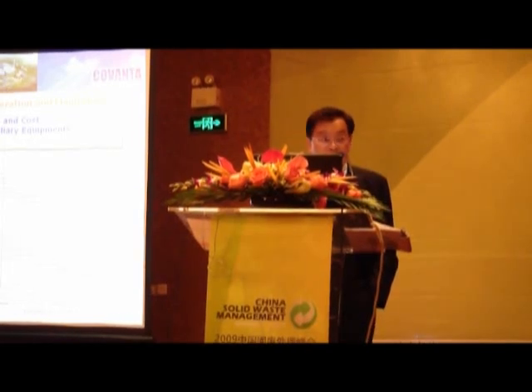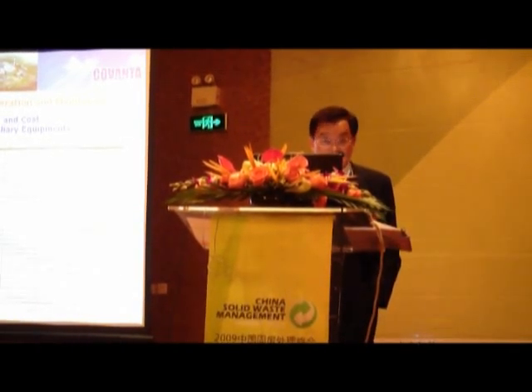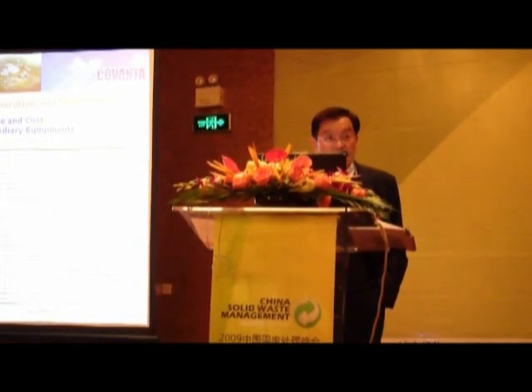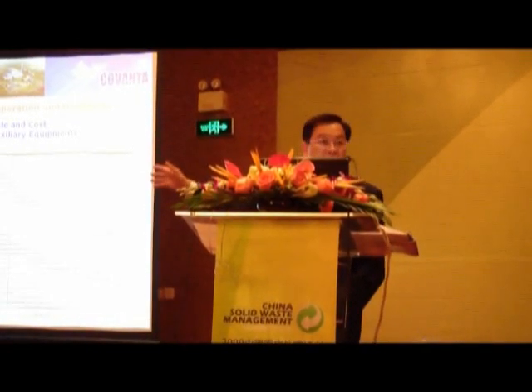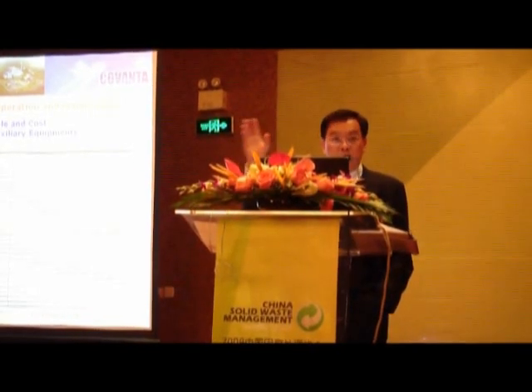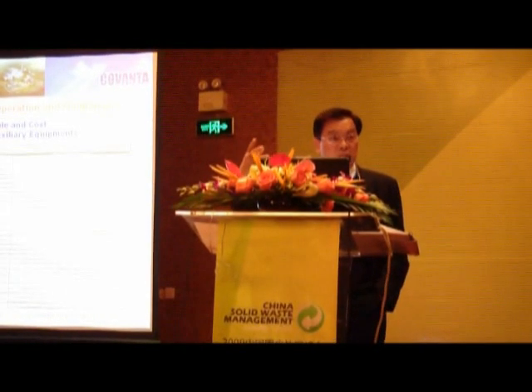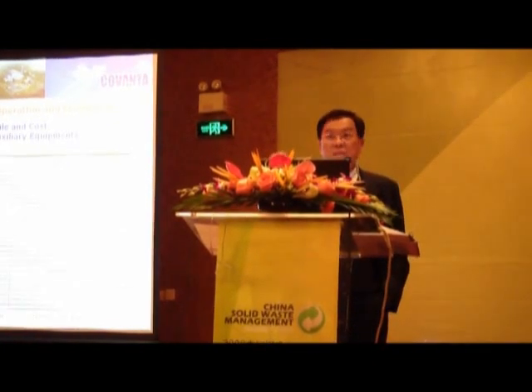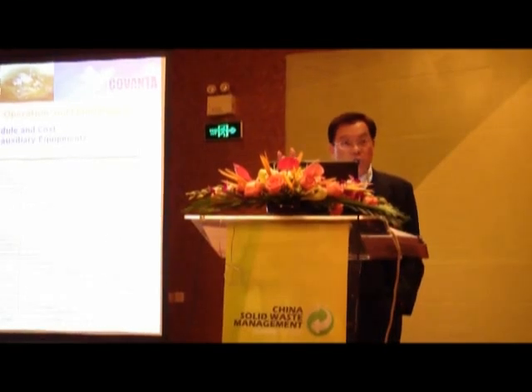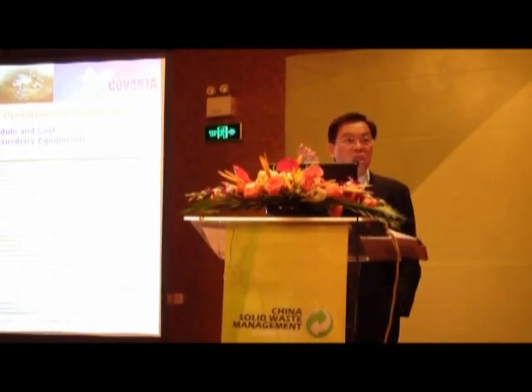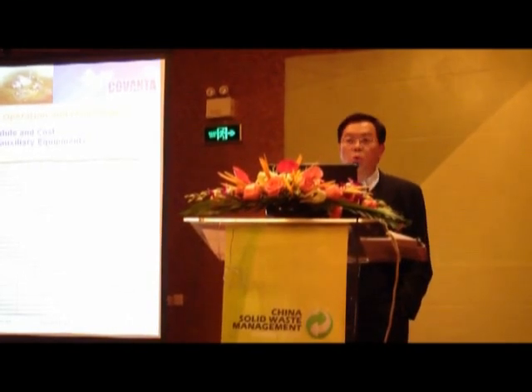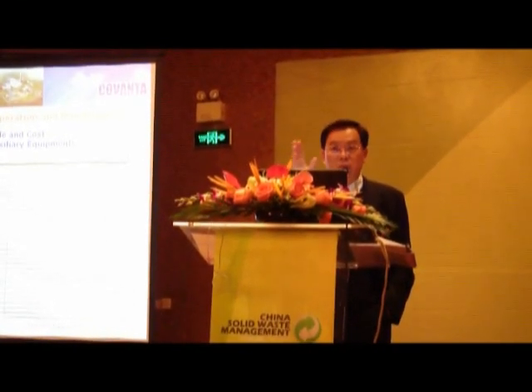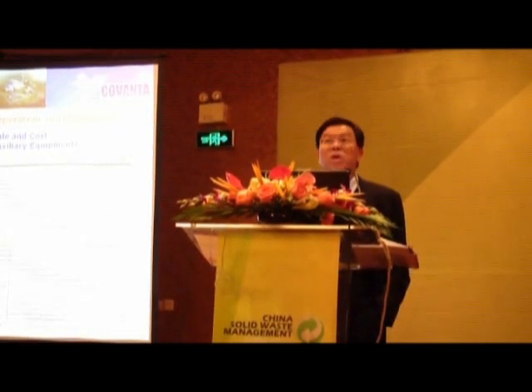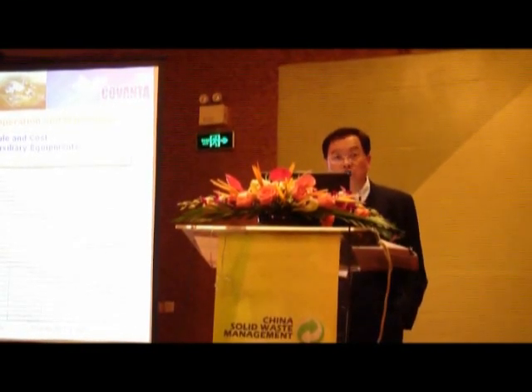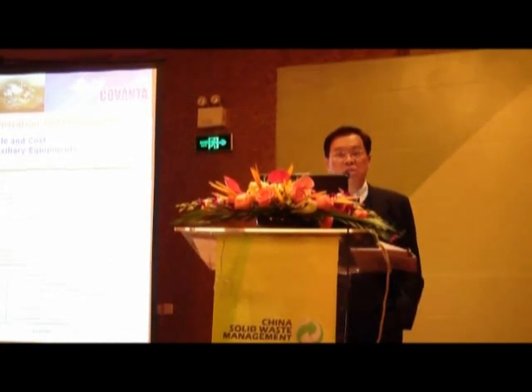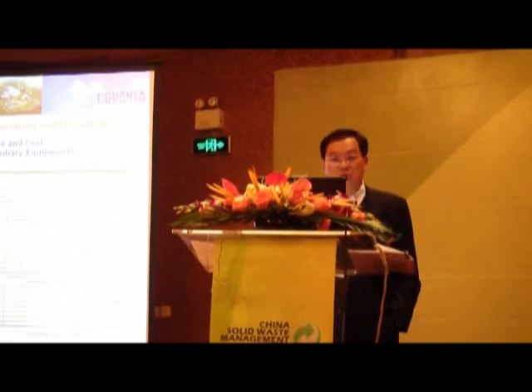Now, again, you break the plant into many more than 100 subsystems, and you need to predict each system at the year 3, year 5, year 7, year 9, year 10, what will happen, what you need to repair, how much you need to replace. And generally, you need to know your plant design, your equipment quality, your construction quality, and the waste quality you're dealing with. Based on all this information, you make a 25 years prediction of which part, which equipment, which system, what do you need to do at which year. That's called major overhaul. And usually an experienced waste-to-energy company can do that at the very beginning, before the plant construction starts.